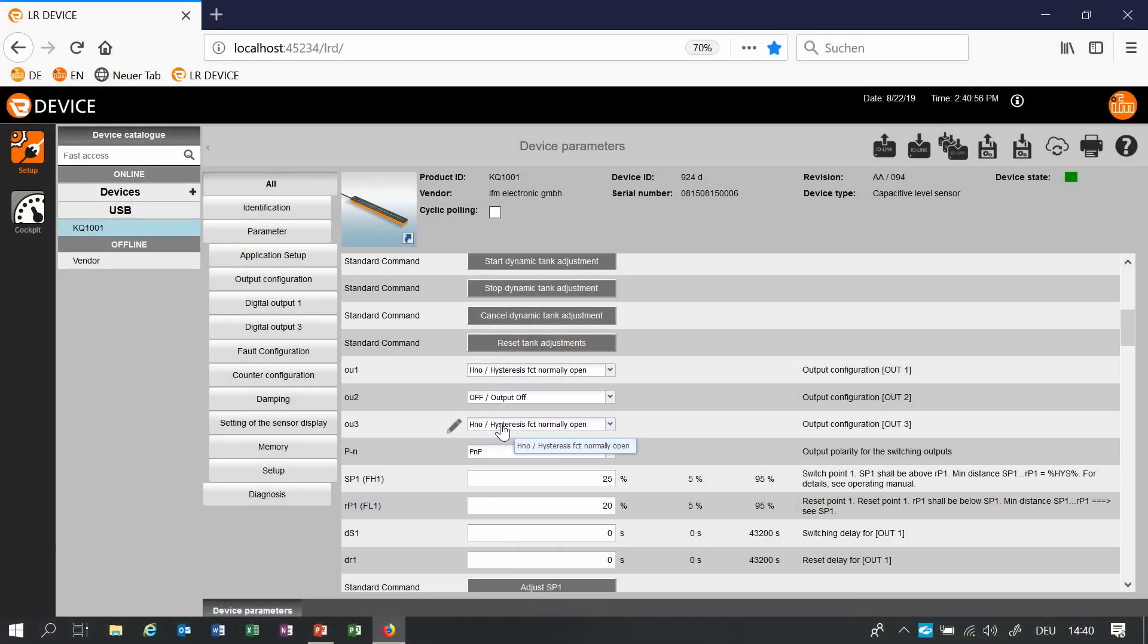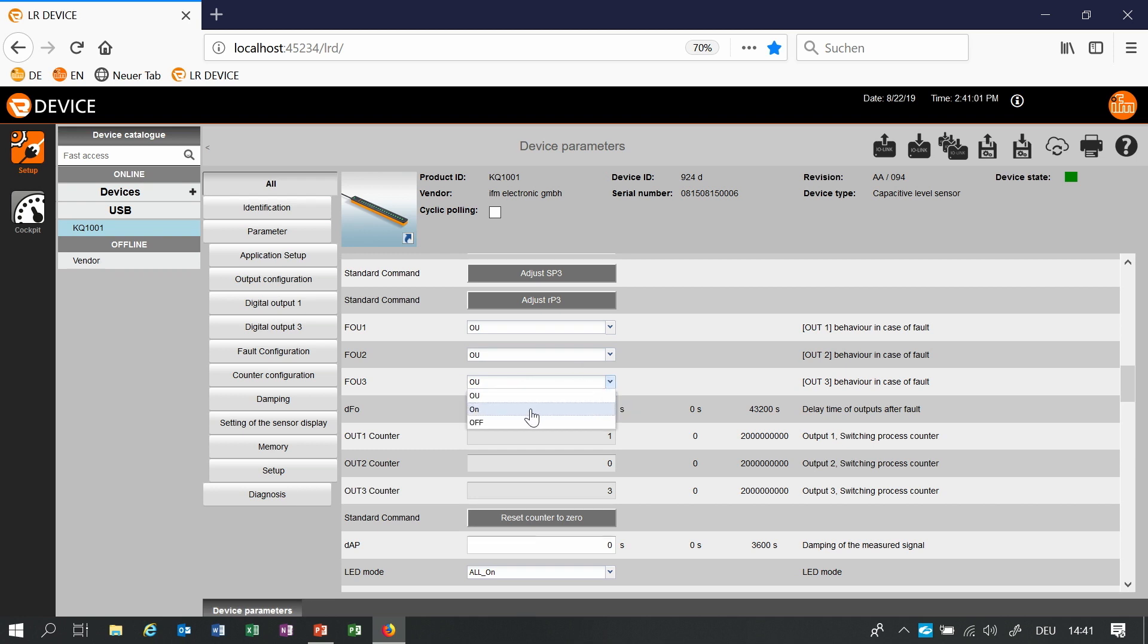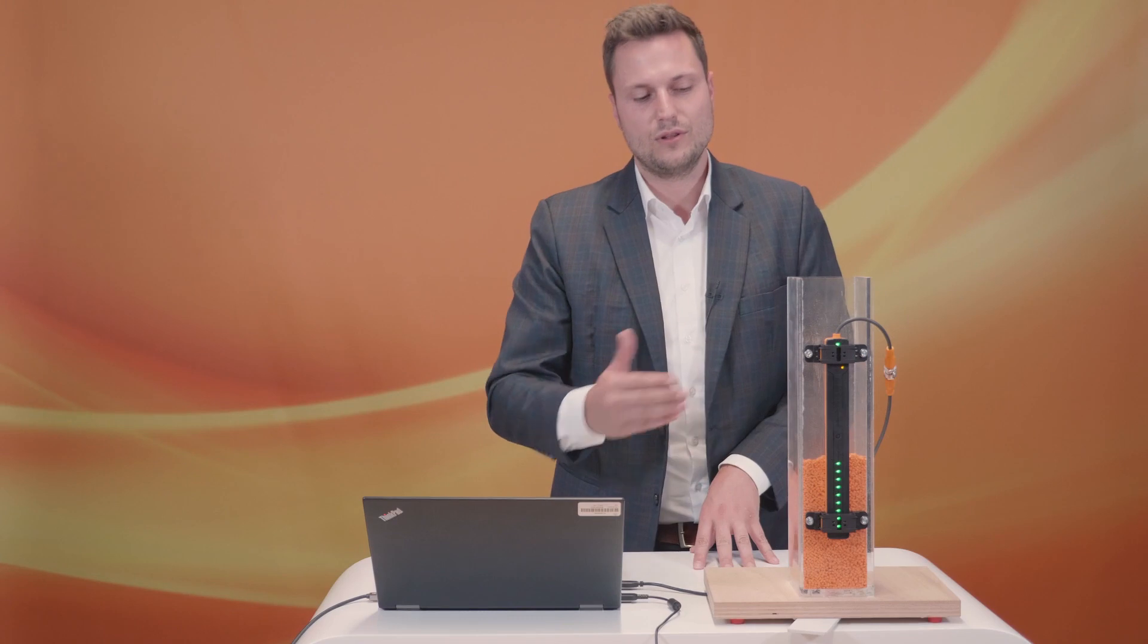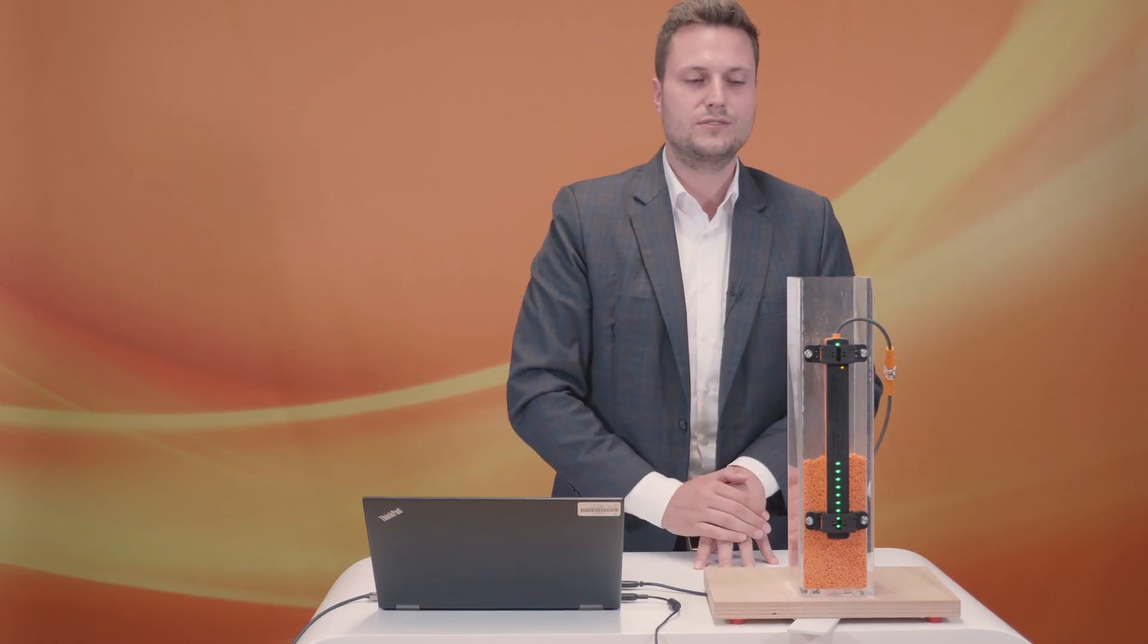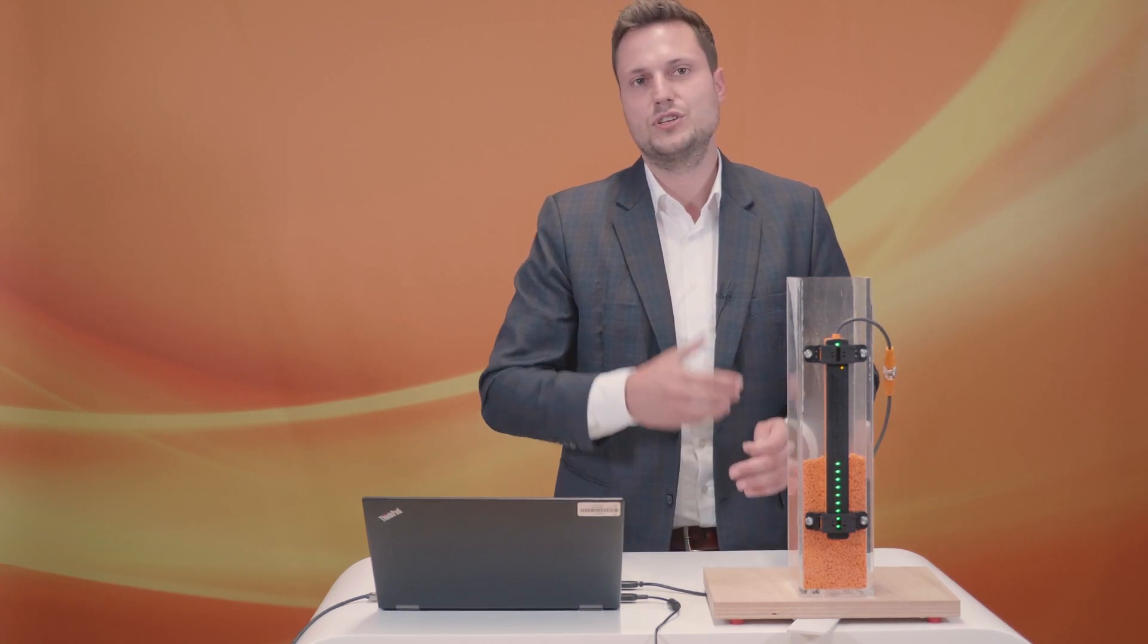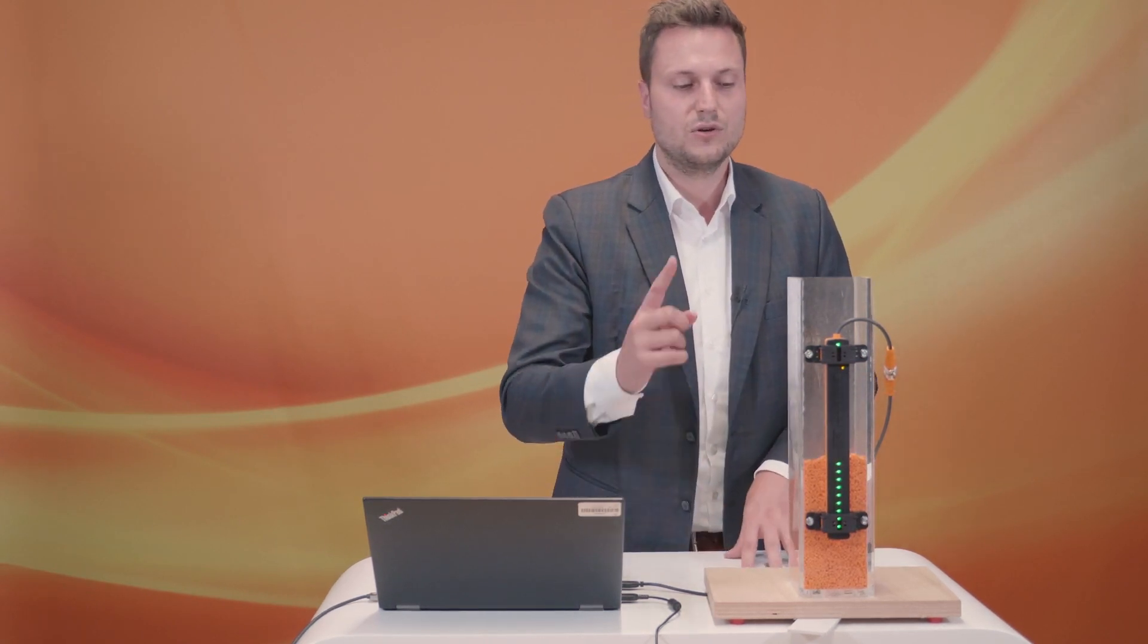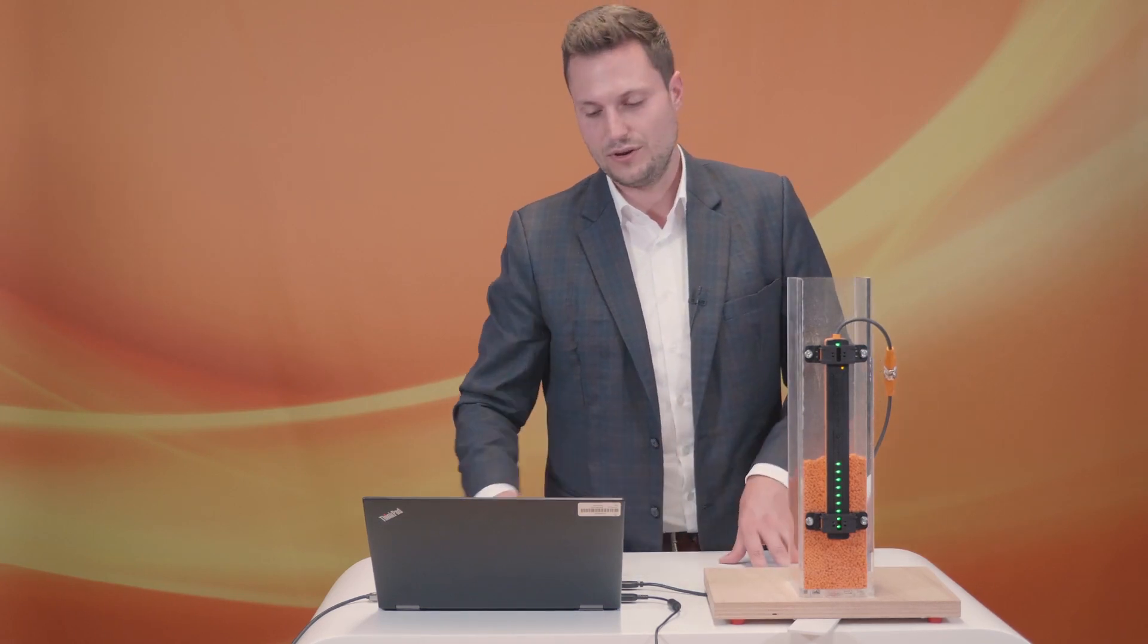We are also able to use one of the switch points for a fault signal. We just have to activate one of the switch points, in this case switch point 3 and set the fault switch point here on off. This is especially for high high application or low low application. When the sensor gets disturbed or maybe detecting something which can't be a level the sensor sets one switch point on.